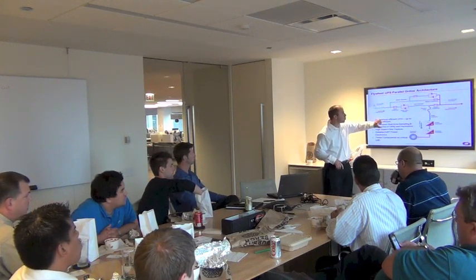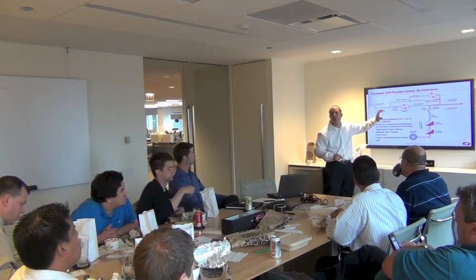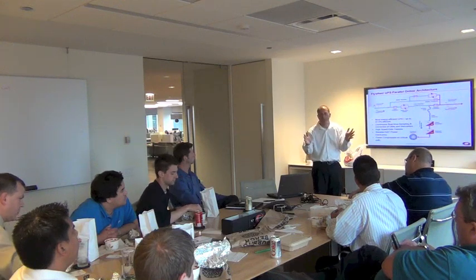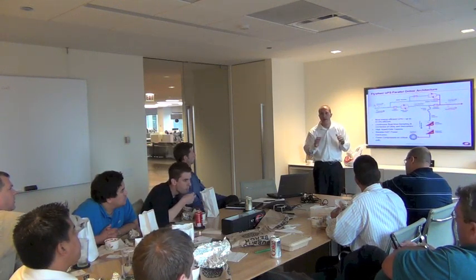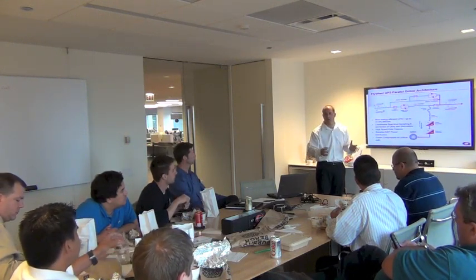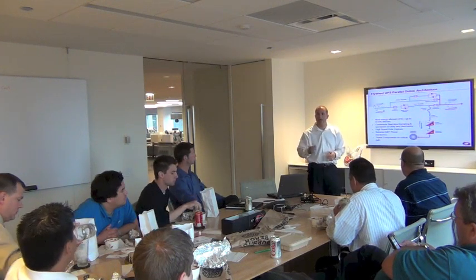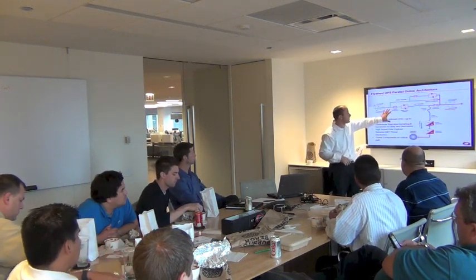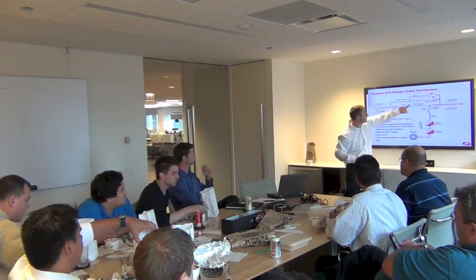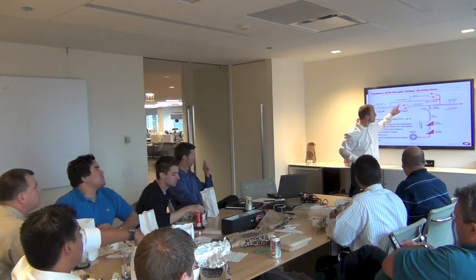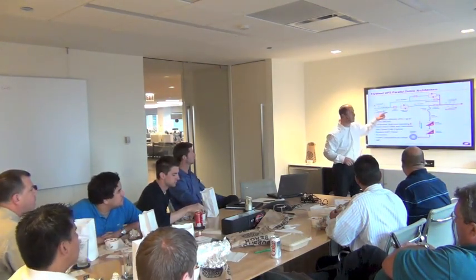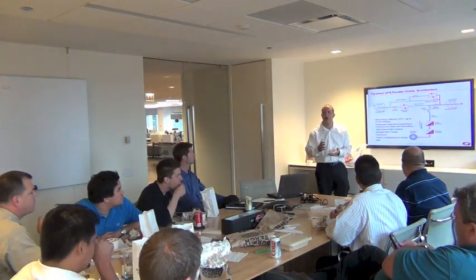And this is kind of a high-level drawing. This would be typical of what we refer to as our single module system, which is just a single 300 kVA UPS. We also have our multi-module system, which is basically you grow in 300 kVA increments. And basically, this is all of the critical components that you see right here, except for the bypass. All of these critical components are distributed in each one of the flywheel cabinets. So it's a very modular design.